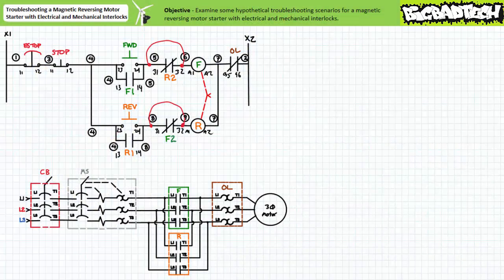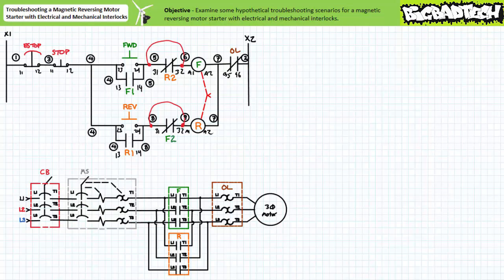While in this energized and unsealed in state, the reversing contactor coil continues to experience high inrush current. If an unusually headstrong operator or a persistent automatic input continue to energize the reversing contactor coil, you might expect this particular coil to burn out. A burned out reversing contactor coil would ordinarily open and exhibit an extremely high resistance. A visual inspection of the coil might show blackened, heat damaged exterior.